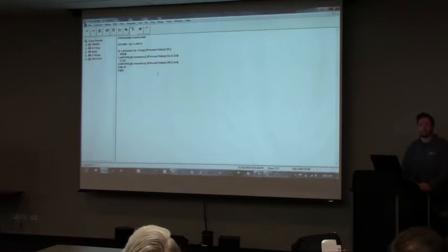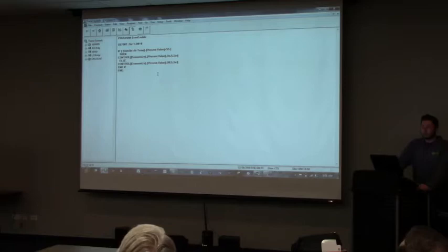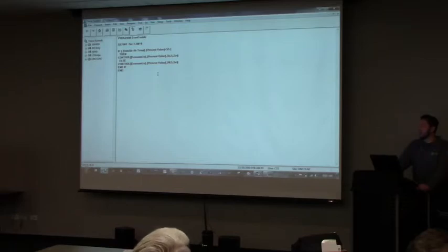If you noticed, when it was reading the point, there was a dot between the object and the property, but when it was controlling the point, it put a comma. Yes, huge difference, and your whole program will fail if you don't have that set up right. I know what to do though if I screw it up: just call Mike or call Tony.